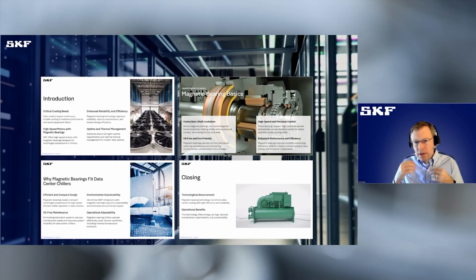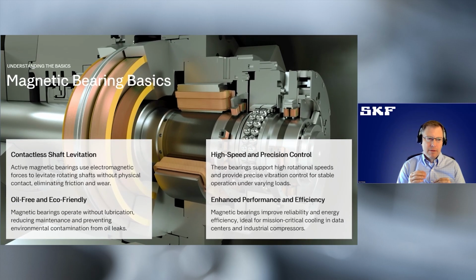I want to talk about some of the basics. What is it about magnetic bearings that makes them such a good choice for centrifugal compressors? The first key point is there's no contact when rotating the shaft inside the compressor, the shaft is levitated using electromagnets. This levitation opens up a host of other benefits: there's no oil, since without contact there's nothing to lubricate, so you get rid of the lubrication system and all the maintenance that goes with it. There's also no wear, because without contact, surfaces don't touch each other and so they don't wear over time.